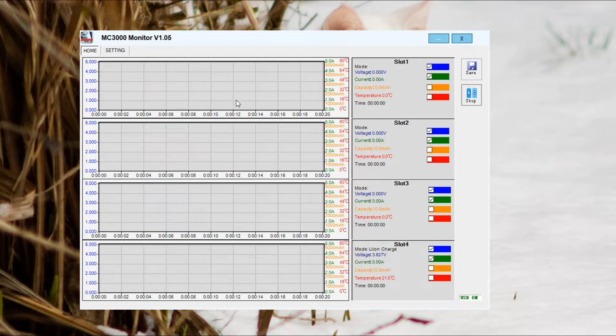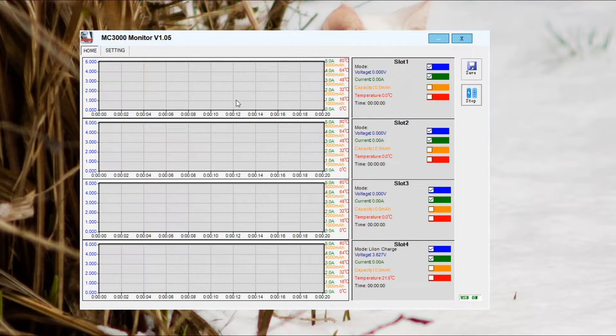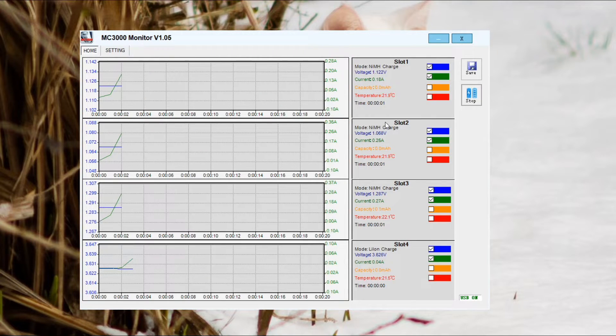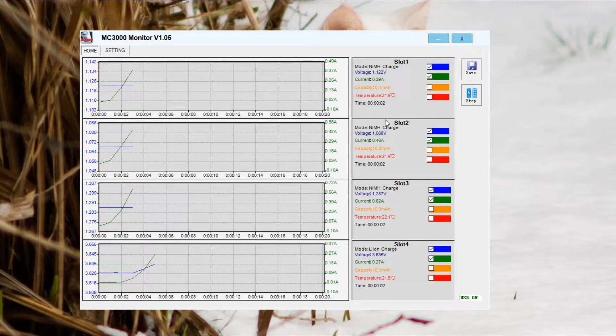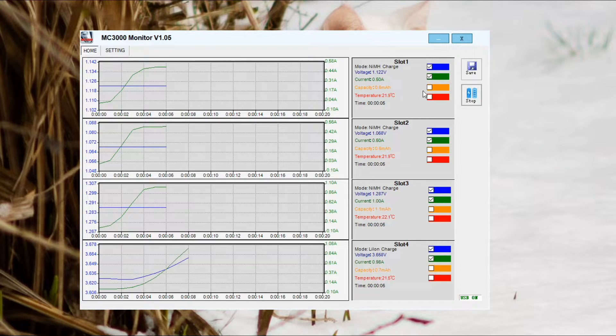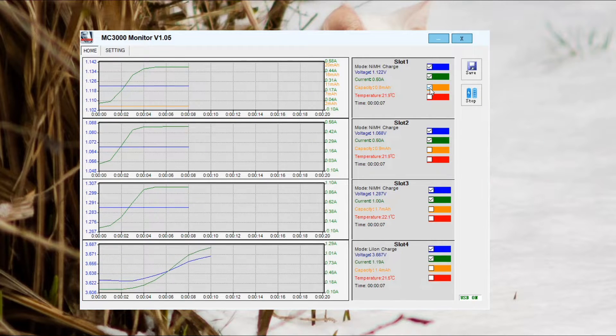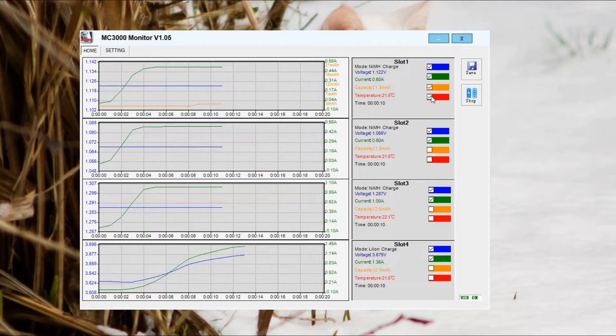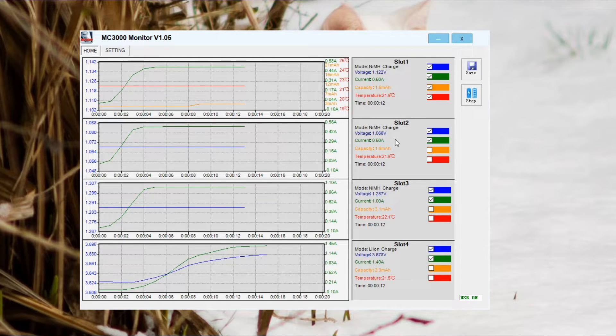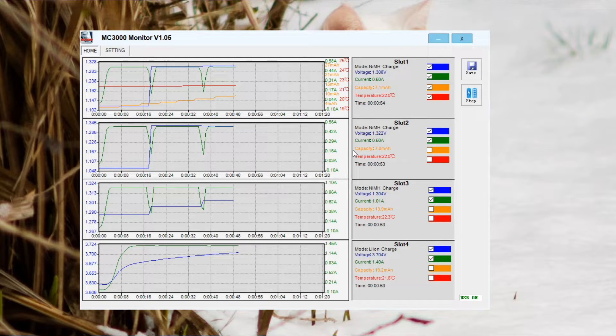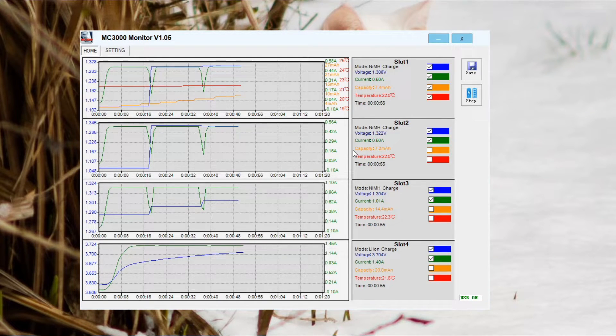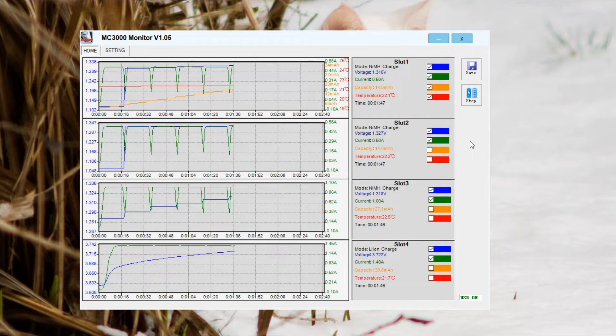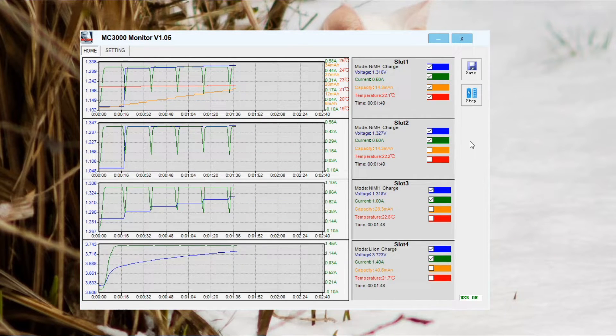Once you've done that, it sends it to the charger. There's a little bit of a delay, maybe five or six seconds, and then it starts to communicate and bring back the data. You'll see the graphs fill up. You have a choice of four on this and they've got different color coding for each one, so you can have just one or all of them together if you want. Over time that scales automatically so it can all fit onto the graph.